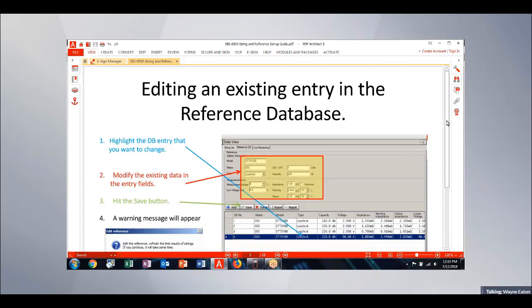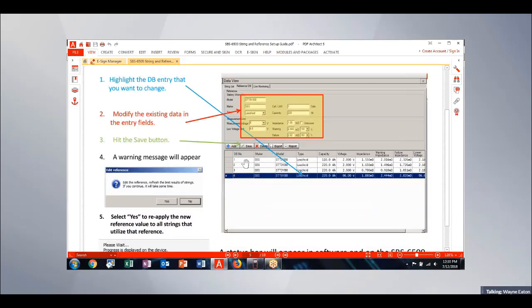Once that database starts to populate, you'll see database entry number 1, number 2, number 3, number 4. I can highlight any of these database entries, and then I can modify those parameters that are inside that entry and hit save. So an example here would be I take that unknown checkbox out, I put in that 1.88 reference value from the manufacturer. When I hit save, it's going to ask me if I want to continue editing that reference, and then it's going to apply that reference value over top of the other strings that are using that as their reference value. So it'll automatically update the results to pass, warning, or fail once I put in what that actual reference value should be.